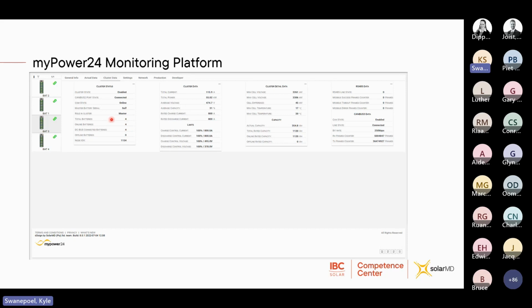And then each battery will have a role in the cluster. There is always one master in the cluster, and this is the battery that will report the information to the control device, so to your inverter or to your charger. The cluster master is not determined by which cable is connected to the inverter. The cluster master is determined by the serial number of the BMU, and the one with the lowest serial number will always be the master. And then each of these batteries will be the slave. So all they do is they report their information to the master, and that has to do with their charge and discharge limits. And then the master will use that information and make the operational call whether to either throttle charge or throttle discharge.